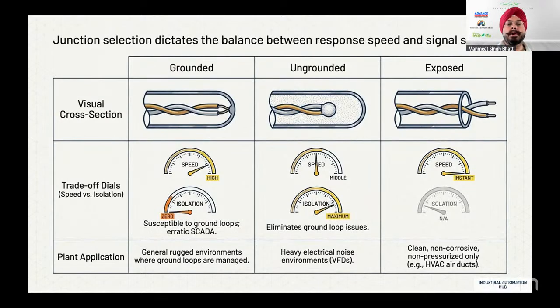Second is called the ungrounded. And you can see the picture from here. The junction is actually not touching the outer section of the walls or the sheath. It's a little bit inside. So it takes some time for the temperature to reach. You will find the response is not very fast. So in this central column you will find the speed is a little lesser, but it's away from the grounding. So any kind of noise which is coming in the ground loop, it's immune to that.